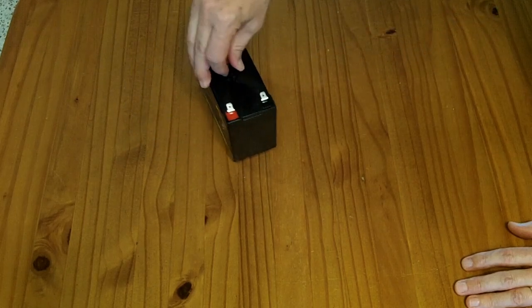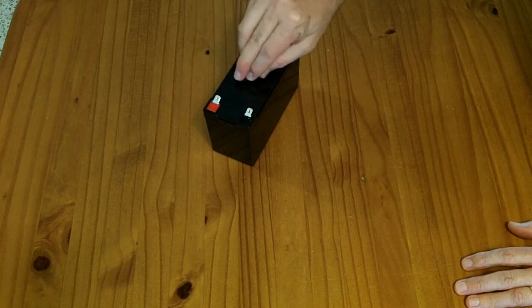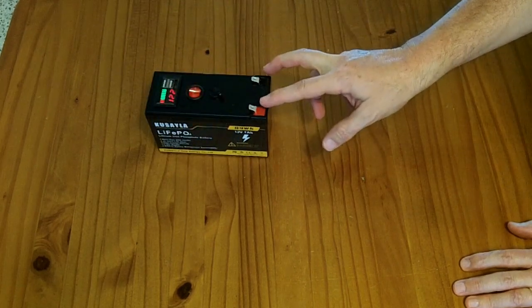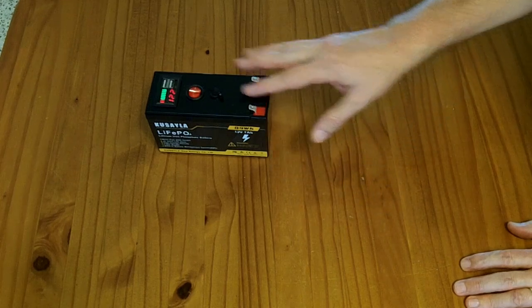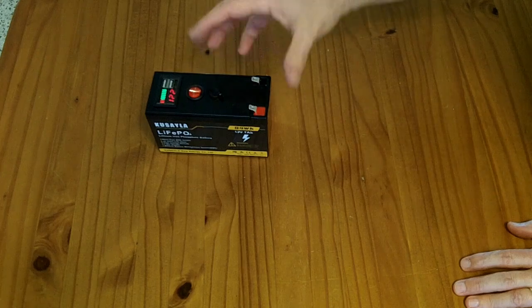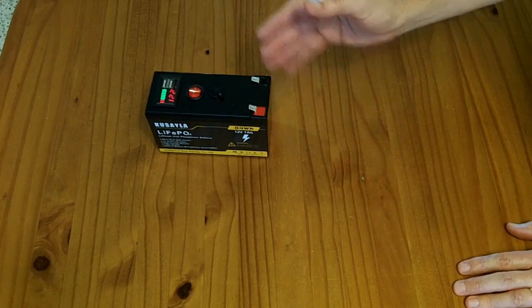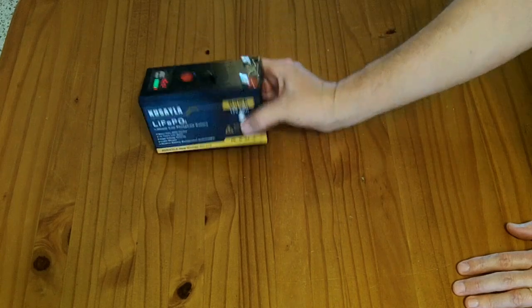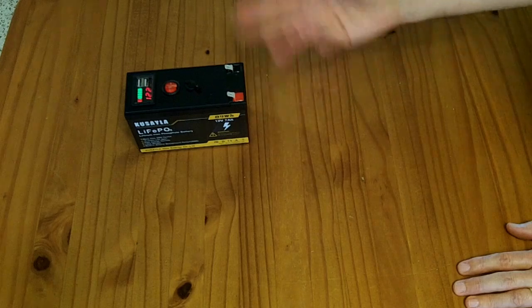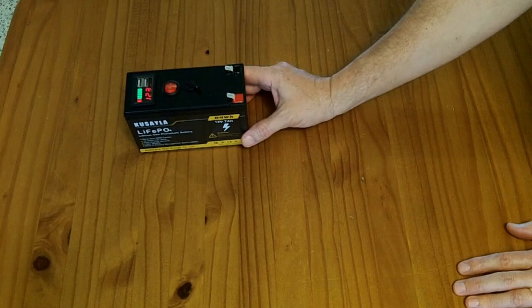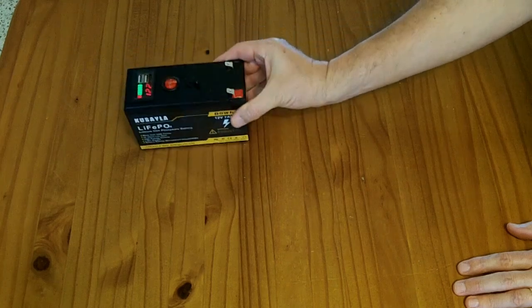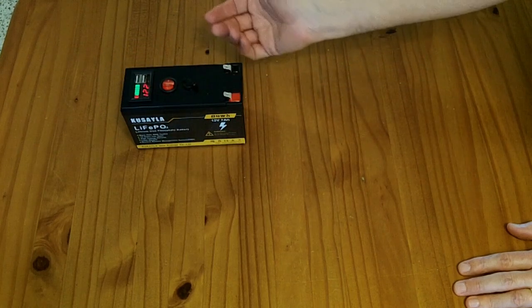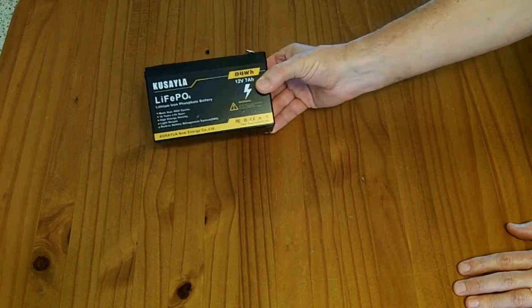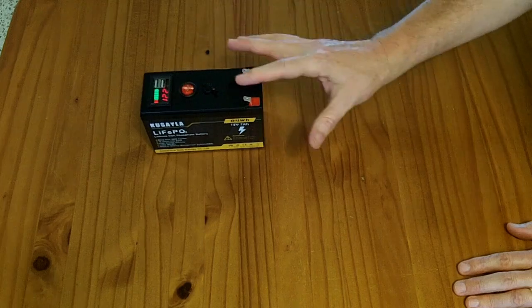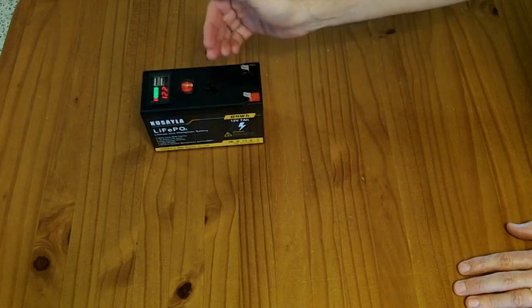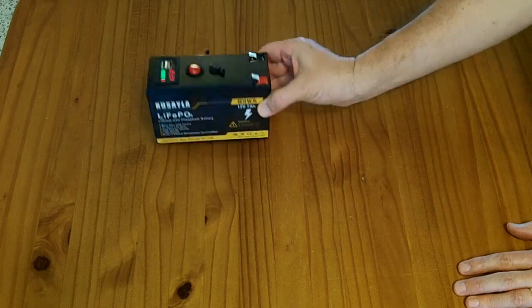Now, charging it, it does include its own charger. You can plug in and charge it up. It also was charging off of my standard lead-acid 12-volt charger, but with that, the voltage would get a little too high, the BMS would shut it off or disconnect it, then reconnect it, charge a little bit more, and so forth. So it might take longer to charge this guy up on a lead-acid battery charger because of the shutdown and startup cycle. I don't know the charging speed on a lead-acid battery charger versus the plug-in charger, but it did look like it was charging off of a lead-acid battery charger. So it looks like if you have an application that charges these guys and keeps them topped up, the BMS will automatically cut that off if the voltage gets too high.